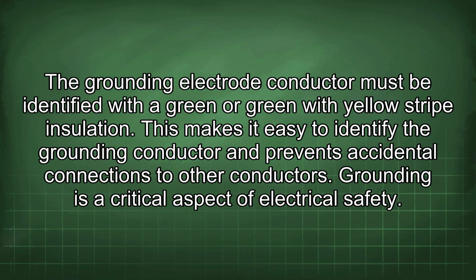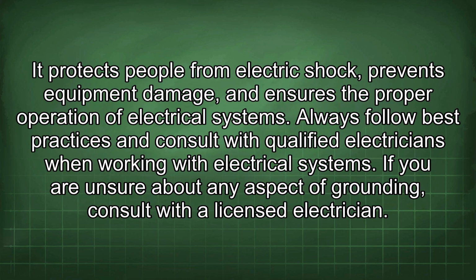The grounding electrode conductor must be identified with a green or green with yellow stripe insulation. This makes it easy to identify the grounding conductor and prevents accidental connections to other conductors. Grounding is a critical aspect of electrical safety. It protects people from electric shock, prevents equipment damage, and ensures the proper operation of electrical systems.